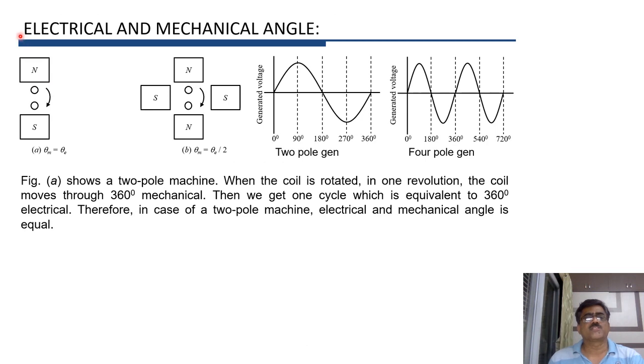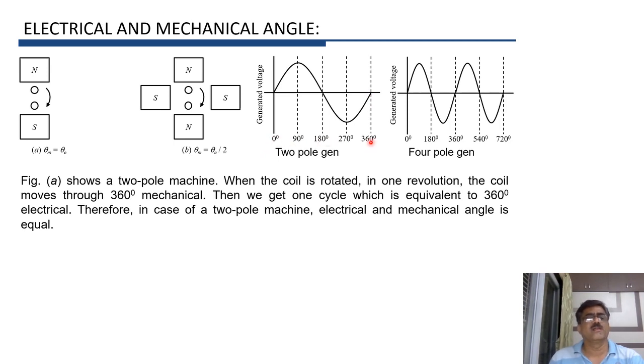The next important concept is the difference between electrical and mechanical angle. In figure A, there is a two-pole machine. When this coil is rotated through one revolution, it is equivalent to 360 degrees mechanical. We get one cycle of generated voltage, which is also equal to 360 degrees electrical. Therefore, in case of a two-pole machine, theta mechanical equals theta electrical.